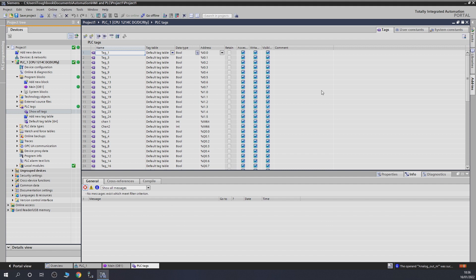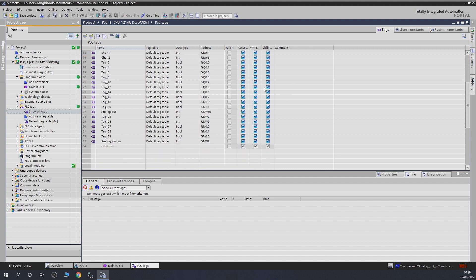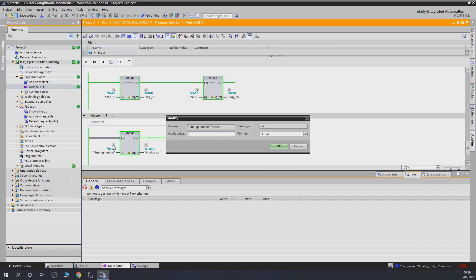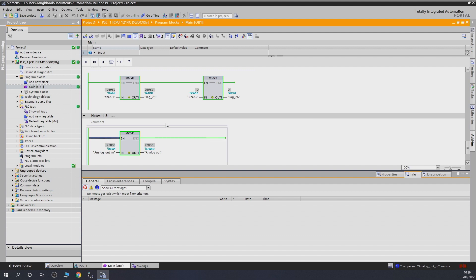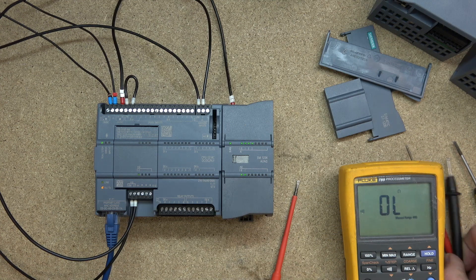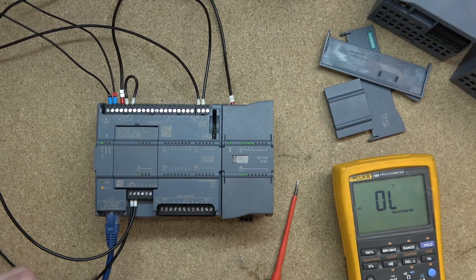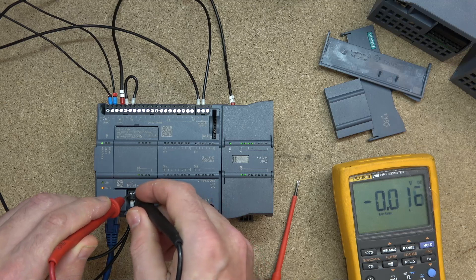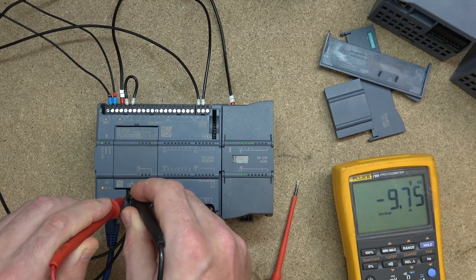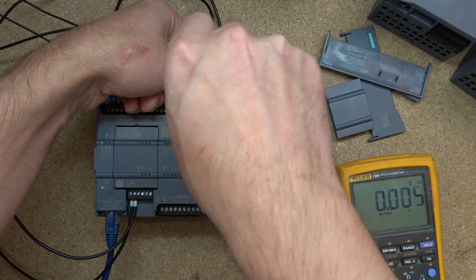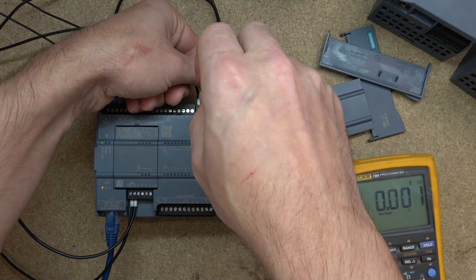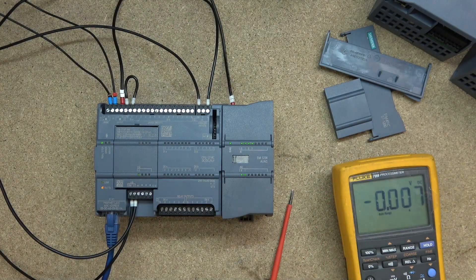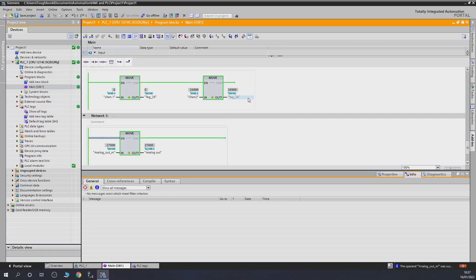So because these are analog values for these particular analog inputs and analog outputs for Siemens, they are something 27,000, zero to 27,000 or something. I'm sure you guys already know it. So let's put 27,000 back in. We double click on that one, 27,000, just to give me a rough idea. So that seems to be coming across quite nicely. So what we're going to do, we are going to jump back on there. We quickly measure that the voltage is coming out correctly. So we are getting 9.75 volts. So that is fine. So let's move and check the second channel. And as you can see, second channel is pretty solid as well.